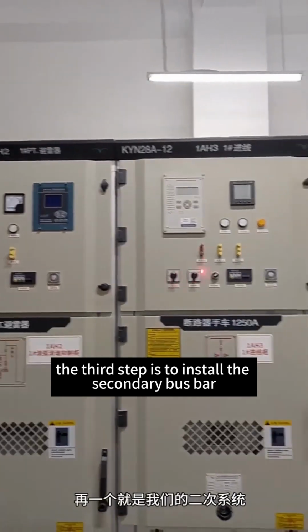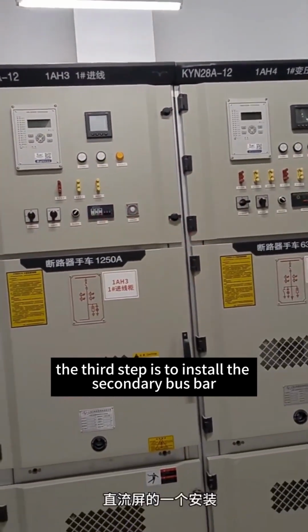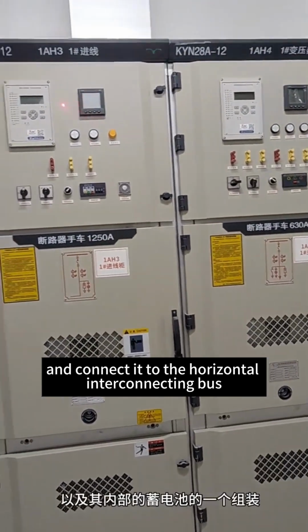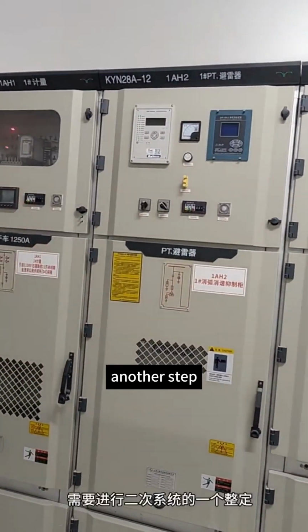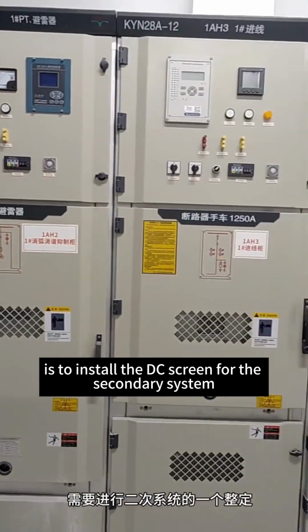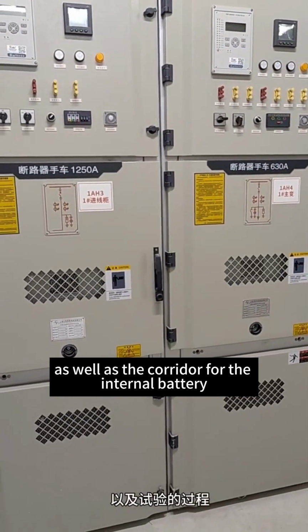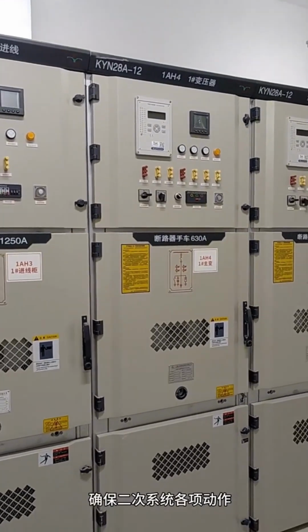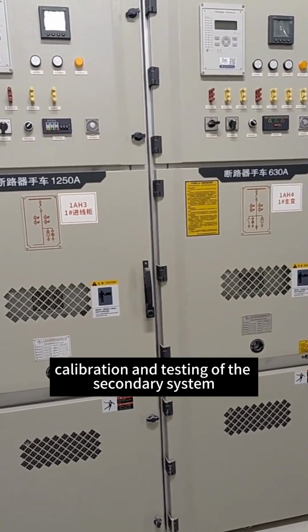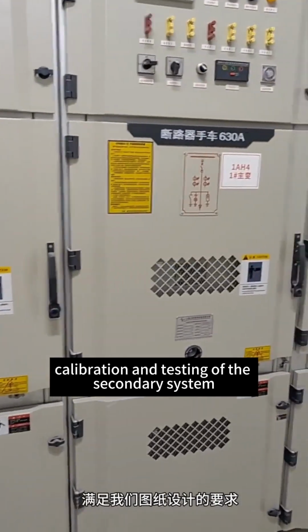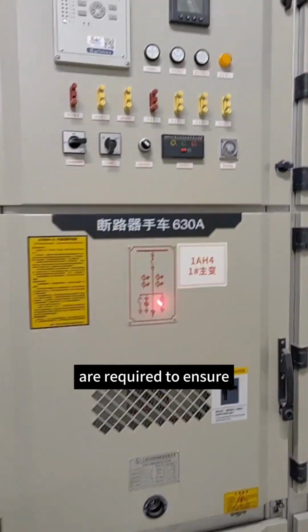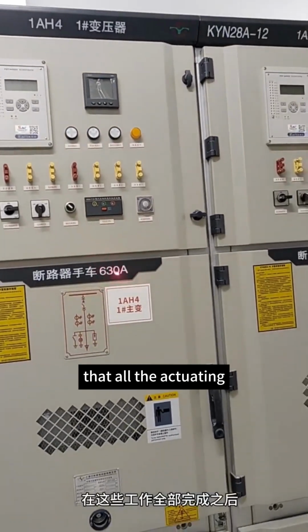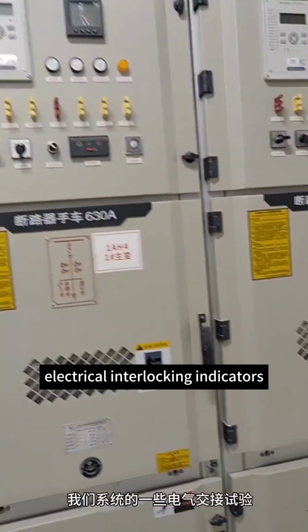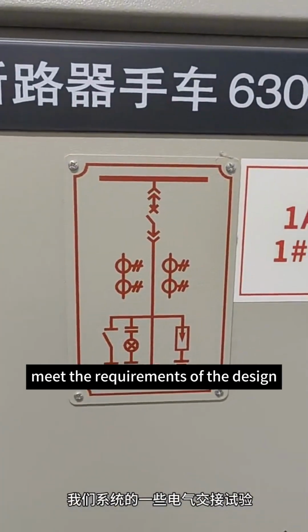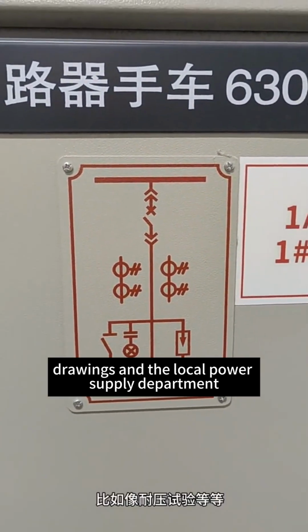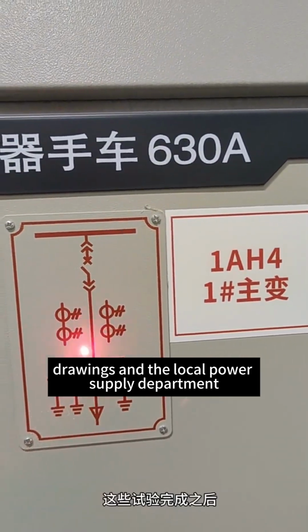The third step is to install the secondary bus bar and connect it to the horizontal interconnecting bus. Another step is to install the DC screen for the secondary system, as well as the corridor for the internal battery. After these steps, calibration and testing of the secondary system are required to ensure that all of the actuating electrical interlocking indicators meet the requirements of the design, drawings, and the local power supply department.